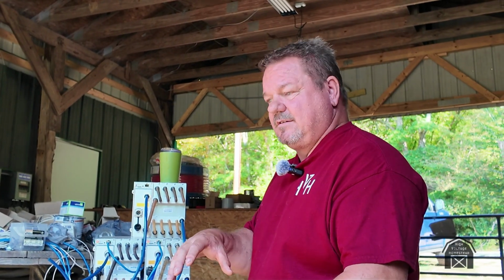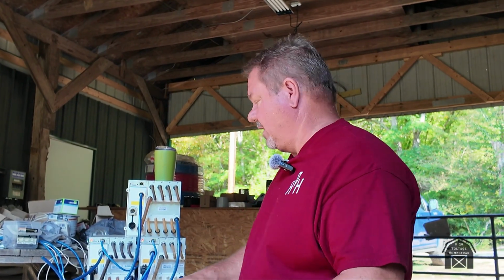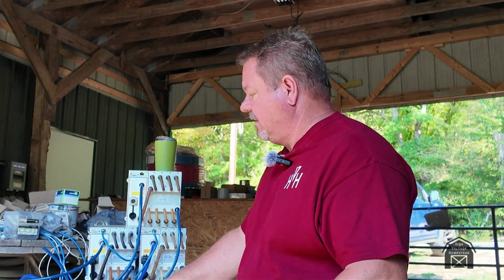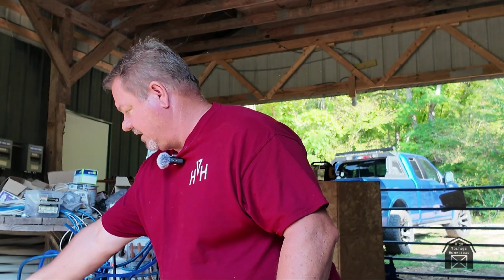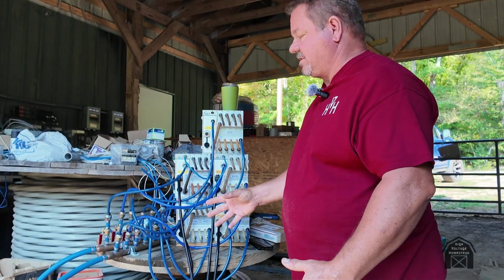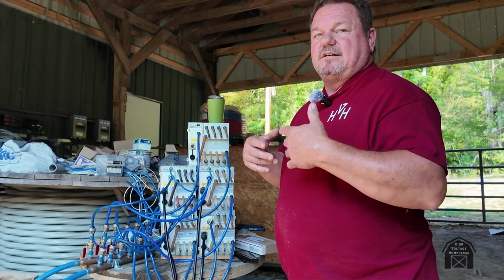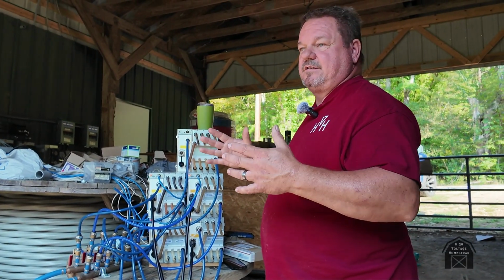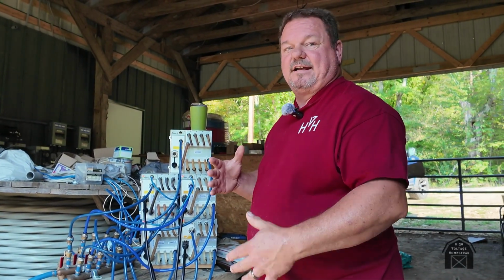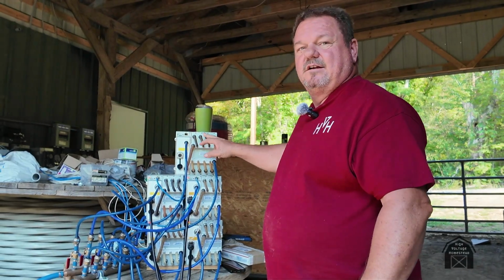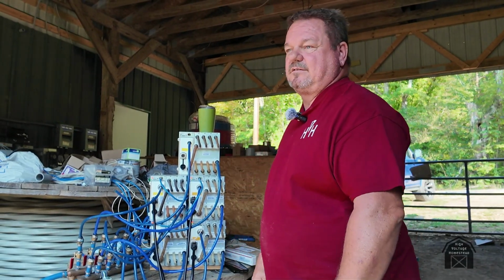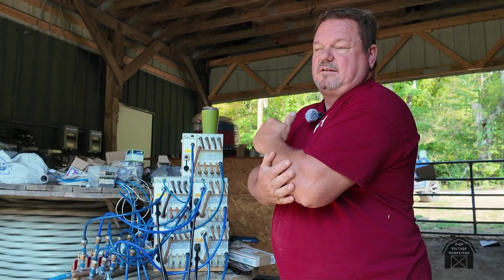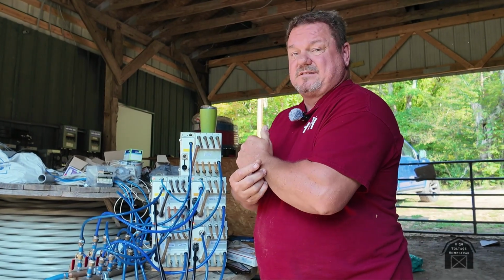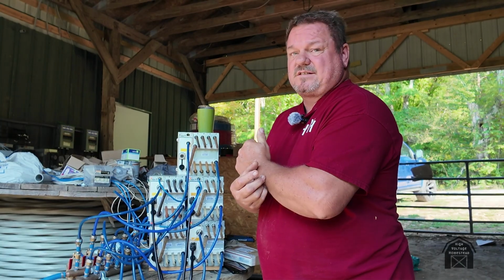I was going to take one of my little recirculation pumps and just drop it in a 5-gallon bucket and run it through the machine for a given period of time - just run it through all of them. Basically hook it up on the supply side, let it pump through all the machines and let that media suck in and cycle through to clean everything back out again, then replace the lines before I put them on the glycol loop. If somebody knows a better way, just leave it in the comments, I'm open to suggestions.